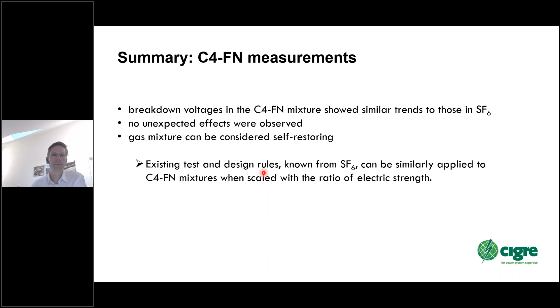So as a summary, the breakdown voltages in the mixtures showed similar trends to those in SF6. We didn't see any unexpected effects, and the gas mixtures can also be considered self-restoring. There was no visible trend of aging, so no deterioration of the breakdown strength with repeated experiments. The existing tests and design rules that we know from SF6 can be similarly applied, of course, scaled with the electric strength of the gas mixture.